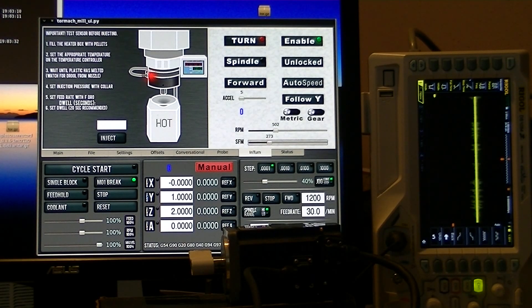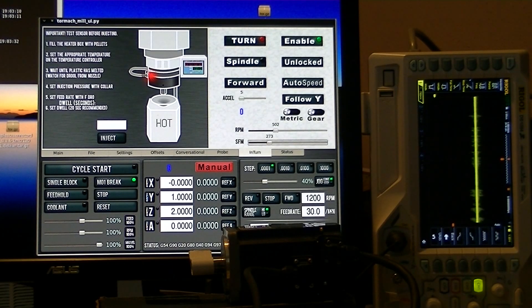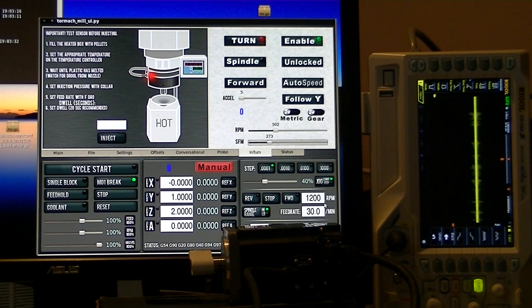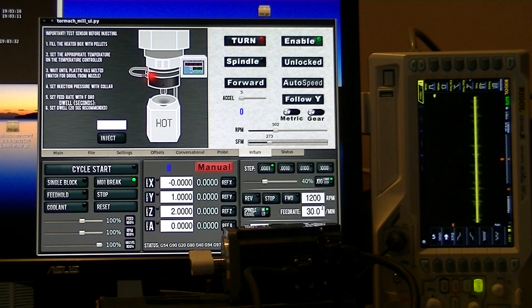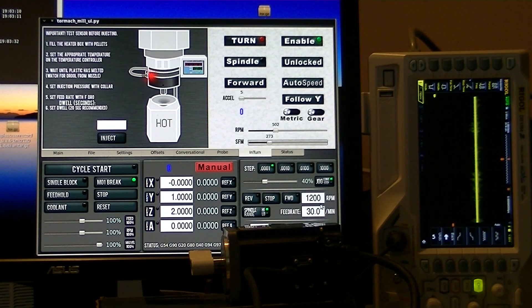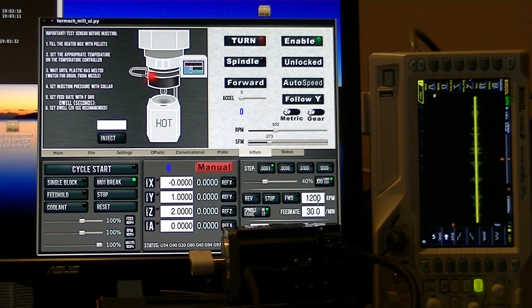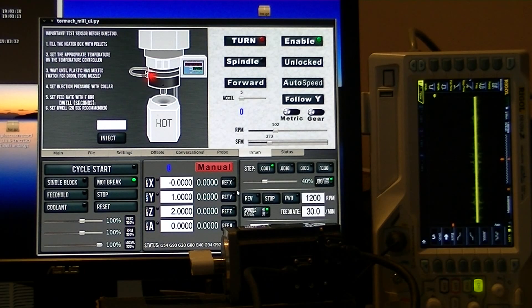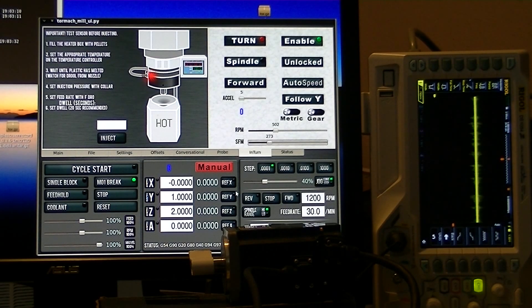How do we make sure that we don't overspeed the motor? If we overspeed the motor, the drive is going to fault and everything's going to stop. One of the parameters that we feed into the controller is the maximum RPM that motor is allowed to go.